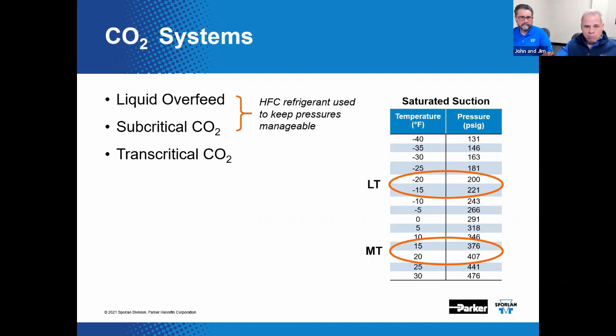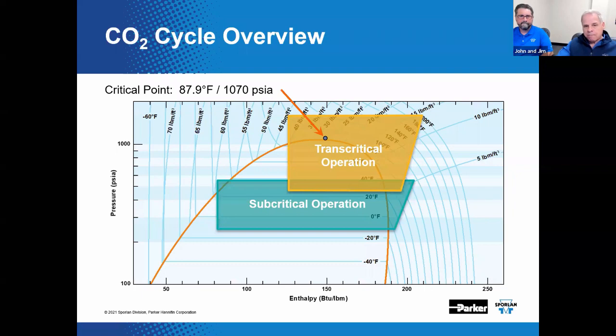Let's take a look at what can be seen on this chart. CO2 operates around 200 PSI for low temp and 400 PSI for medium temp. In a subcritical operation, typically either liquid overfeed or a cascade system would be used. Liquid overfeed would use a pump to circulate liquid CO2 throughout the display cases at the required temperature. And a cascade system would use compressors to produce the desired saturated suction and reject heat to the DX high side rack. Make sense? Let's explore this a little more.